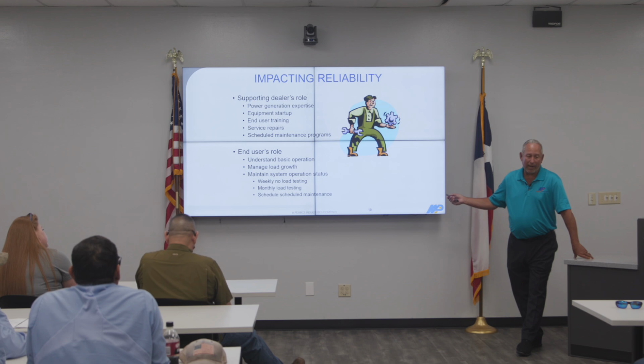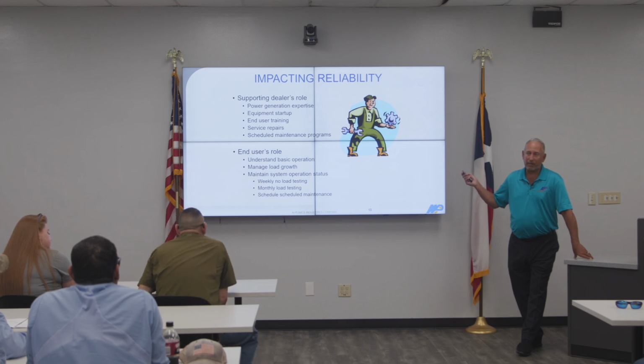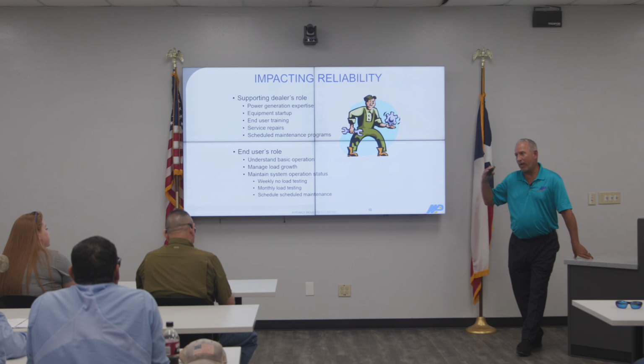It's to the point that NFPA, the National Fire Protection Association, actually has it specifically spelled out what test is required when it comes to healthcare. They want monthly, they want weekly, they want it with load. If you don't have enough building load at your facility, they want you to bring in a load bank at the end of the year. So they've spelled it out.